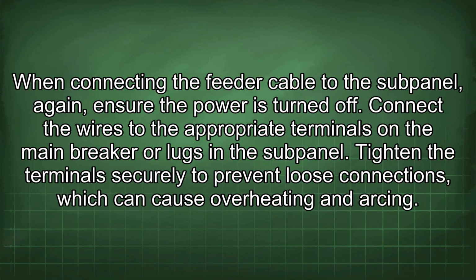When connecting the feeder cable to the subpanel, again ensure the power is turned off. Connect the wires to the appropriate terminals on the main breaker or lugs in the subpanel. Tighten the terminals securely to prevent loose connections, which can cause overheating and arcing.